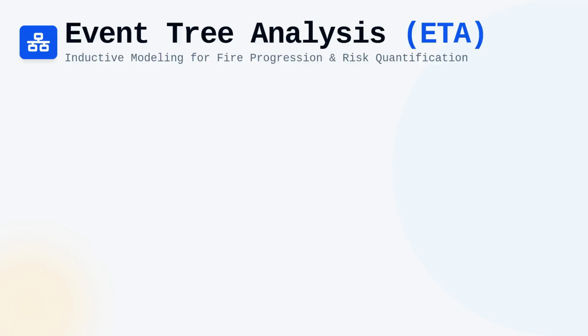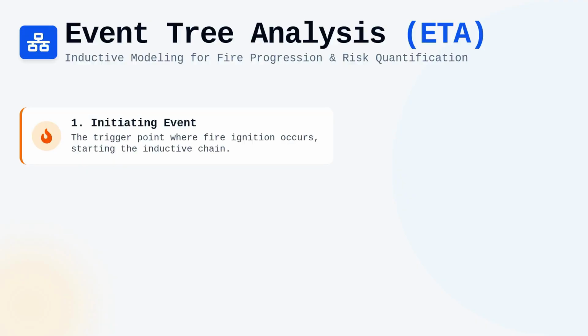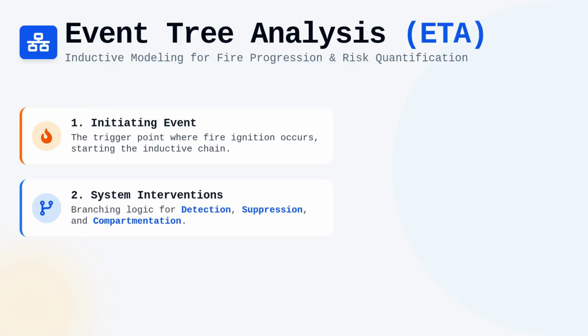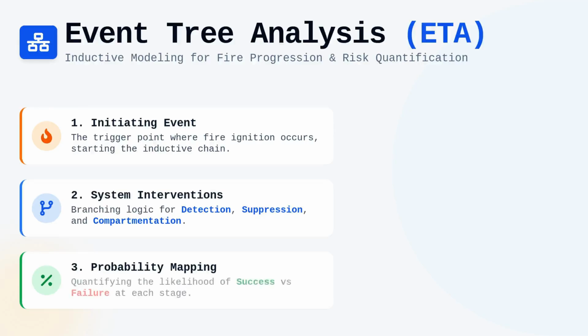If FTA is our deductive tool, event tree analysis, or ETA, is our inductive partner designed to model the progression of a fire once ignition has occurred. We start with an initiating event and follow the branching logic of system interventions, such as detection, suppression, or compartmentation activation. This logic reveals the conditional probabilities inherent in a fire event, allowing us to quantify the likelihood of success or failure at every stage of the incident timeline.